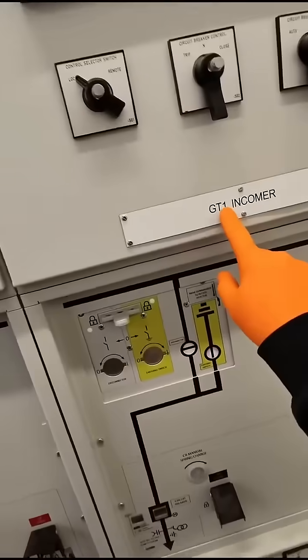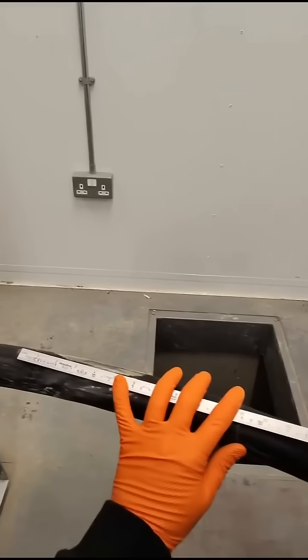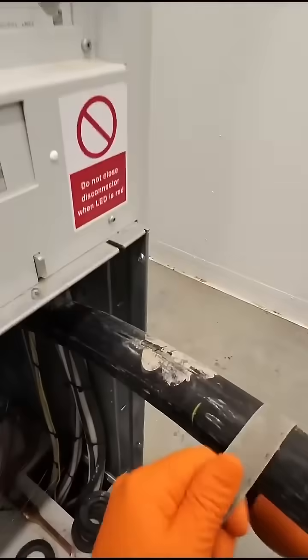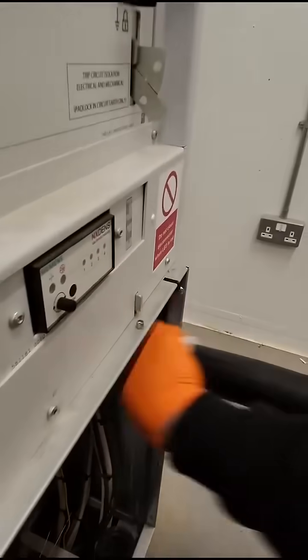Let me show you a full termination for this GT1 Incomer. As you can see, the manufacturer's instruction is a Nexans T-Boot. I've started off measuring the bushing, measuring back 285mm and sanding the insulation by 65mm. This is to help create a watertight seal, and now wipe it with a PF wipe.